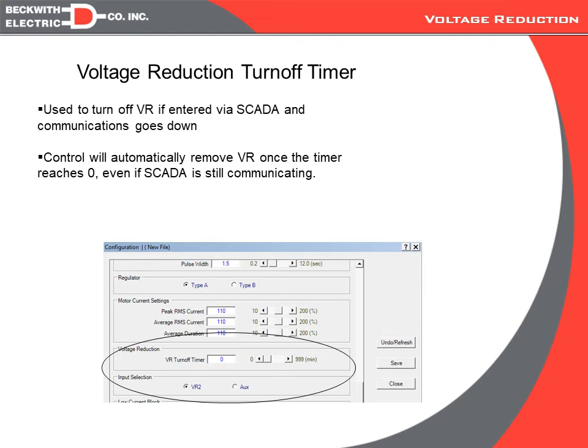So if I were to select this as an auxiliary input, now if VR2 is high, that is not going to trigger a voltage reduction, and we should not see the voltage reduction light come on in the front of the control if that VR2 input is active. So it's a way of using one of the two voltage reduction hardware inputs for other purposes, but still allowing you to do voltage reduction via communications.